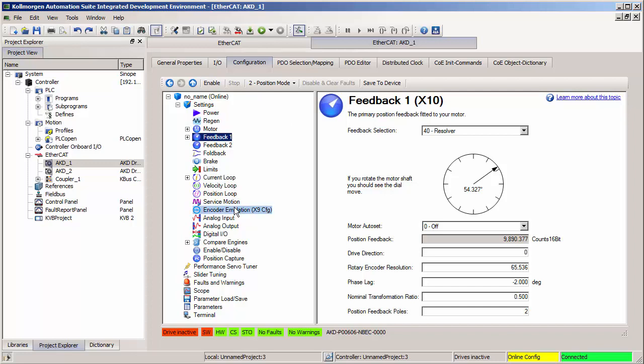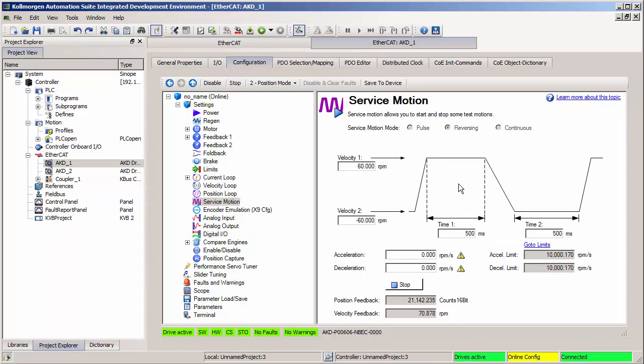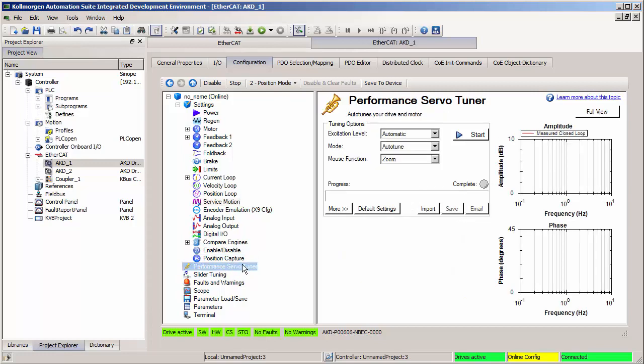We also have access to the service motion screen, where if your drive is enabled, you can start basic moves that are helpful when you're trying to work out tuning. Also, we have the performance servo tuning screen, which is now available and is hidden when a program is running. This is where our auto-tuner is held, which is a great tool to automatically populate tuning parameters and filters for the current velocity and position loops.